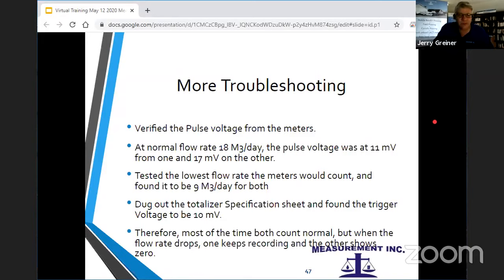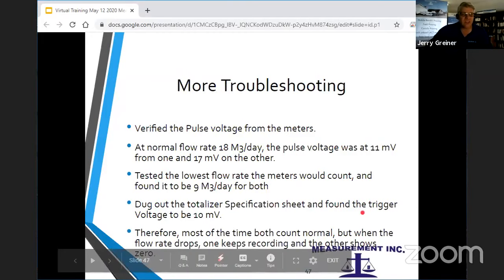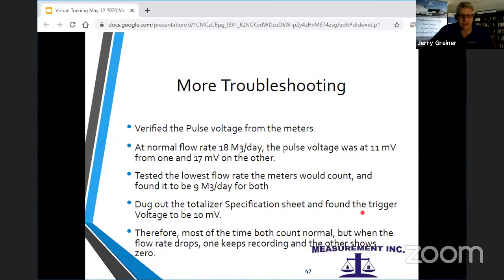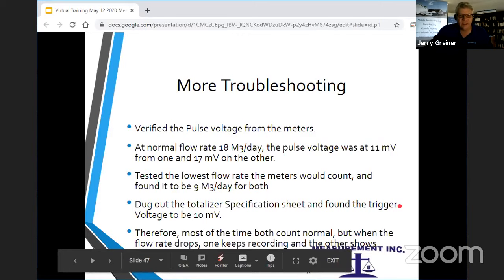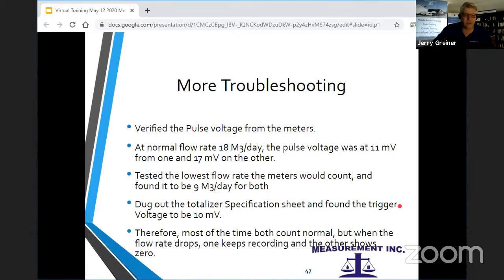When they were on our shop prover, we could go slower. You know, they both count fine to 9 cubic meters. So that's below what they would ever normally see in the field. And then we dug out the specifications and we found the trigger voltage for this particular type of totalizer they had was at 10 millivolts. And it's like most totalizers you see will have a trigger voltage you can change. Sometimes it's selectable. You know, new flows would be selectable, high sensitivity, low sensitivity. The low sensitivity is usually about 4 millivolts or 3 millivolts, somewhere in there. Some are 2 millivolt trigger voltages. 10 millivolt is very high trigger voltage.